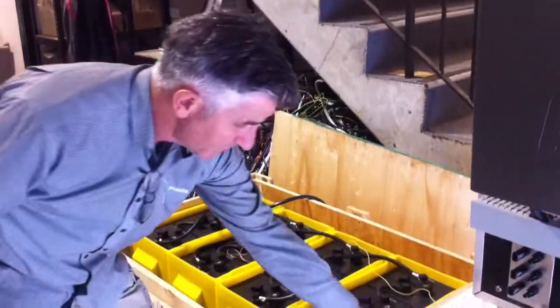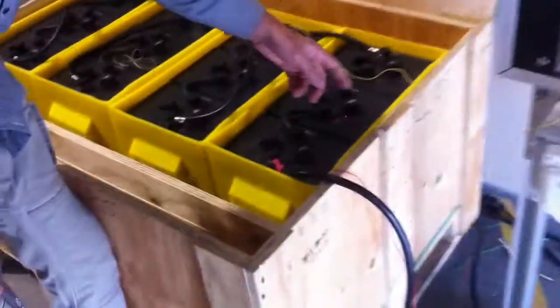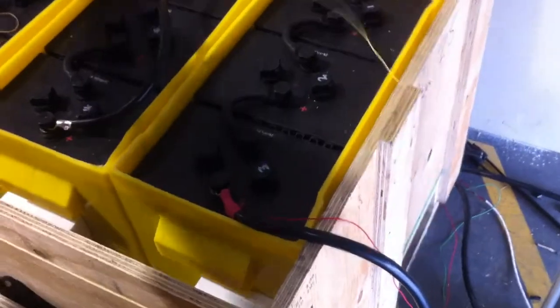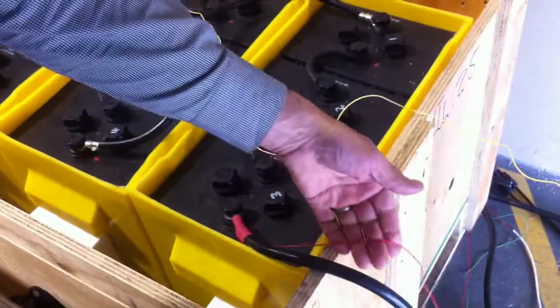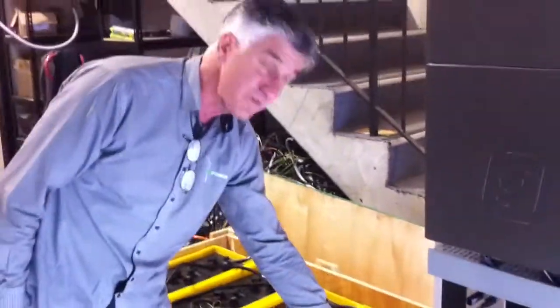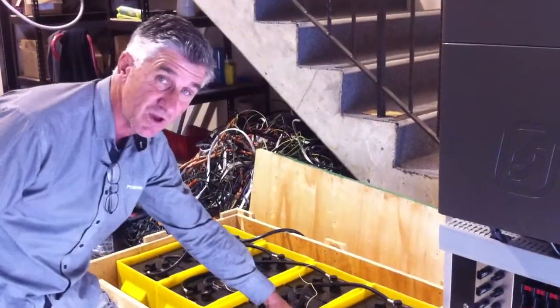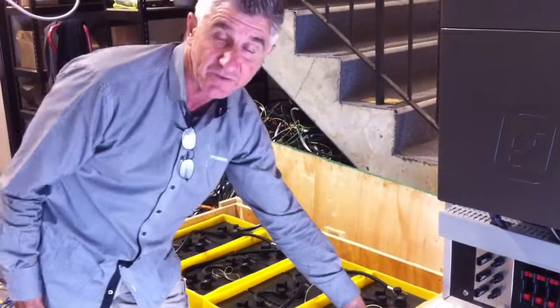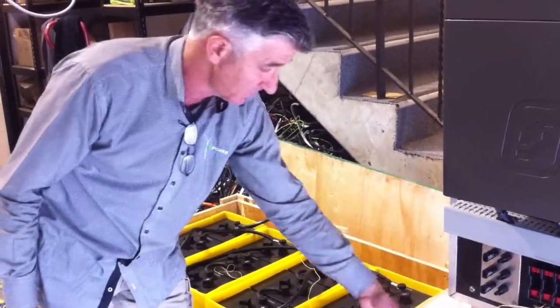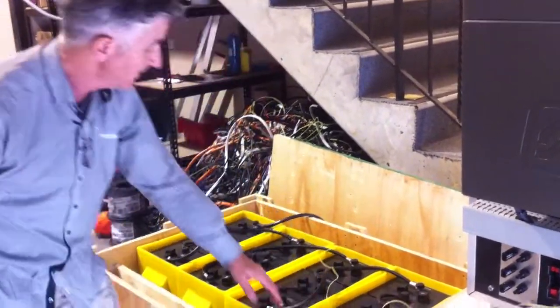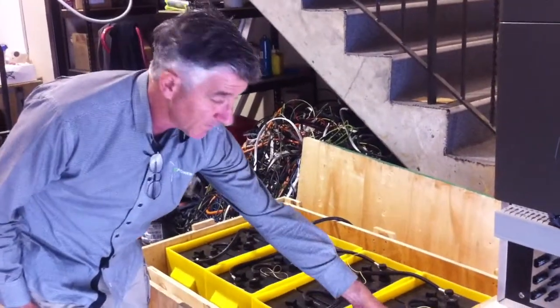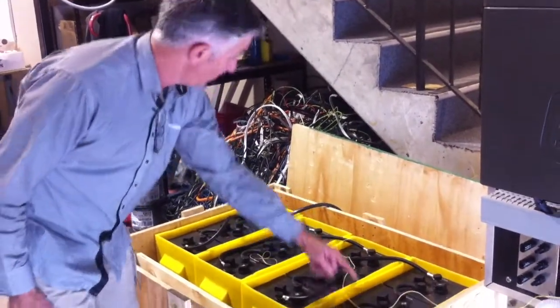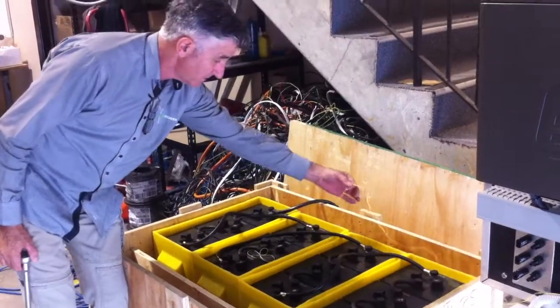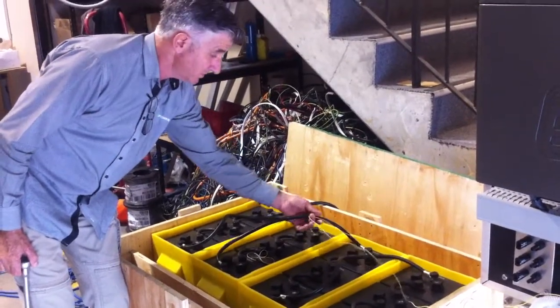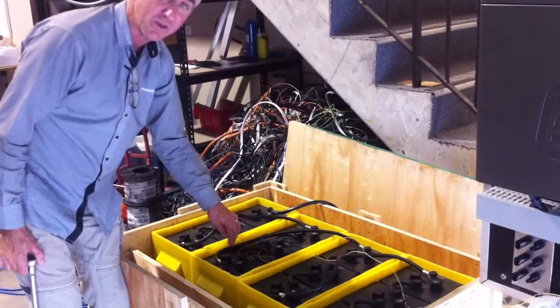Now you'll notice on the positive and negative cable, and on the mid cable which I'll show you in a second, these are called midpoint sensing for the SP Pro. It's very important that these are connected. We've put them in these lugs so you can't go wrong, but don't discard them or cut them off thinking they're just a scrappy piece of wire - they're very important. So you've got a midpoint sensor on positive, on negative, and your midpoint cable, the yellow cable, is on your centre link.